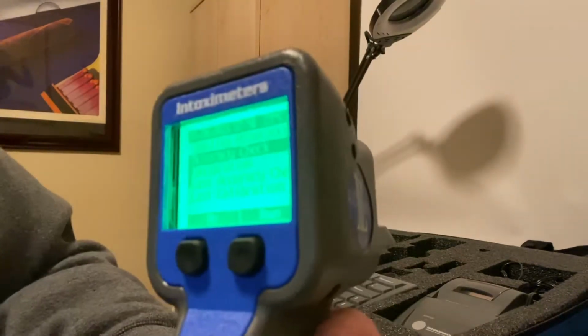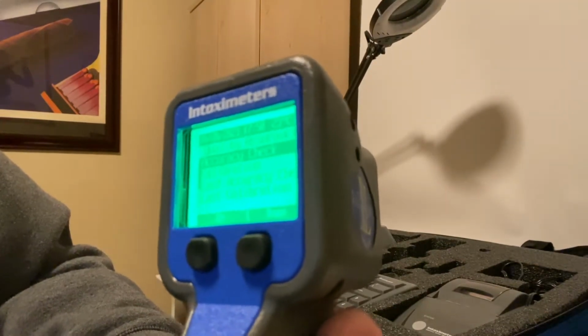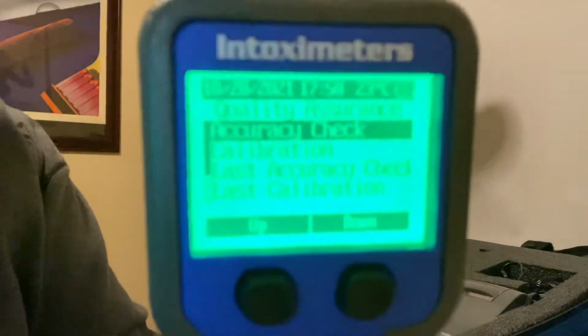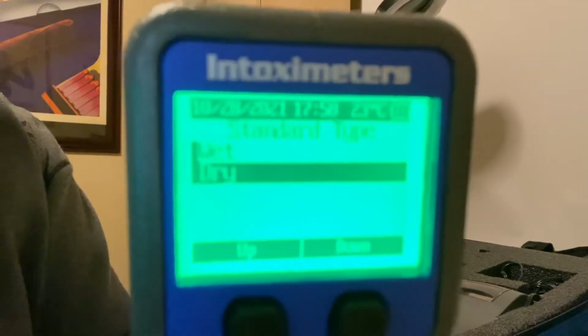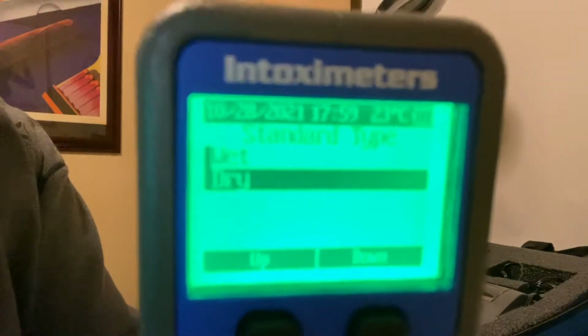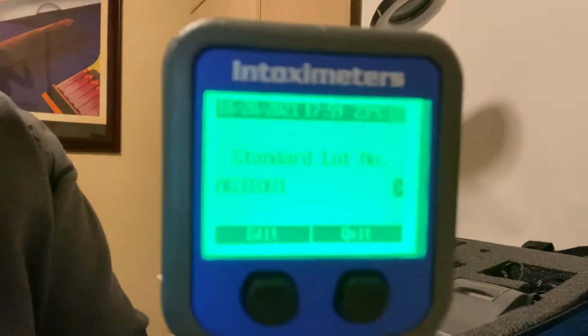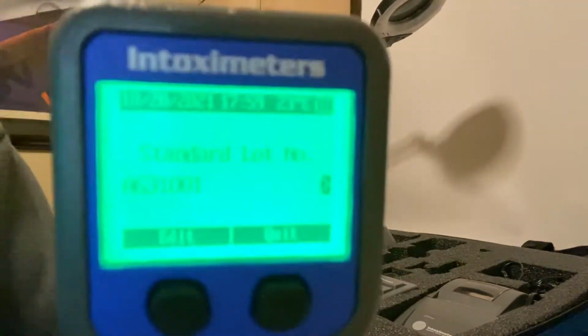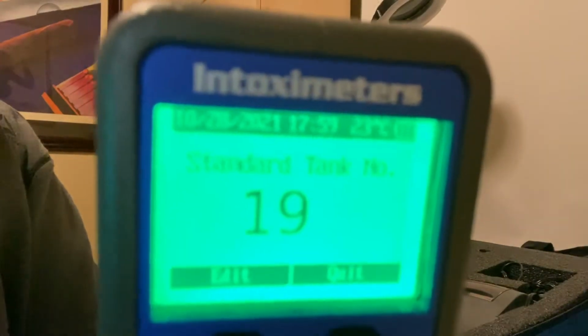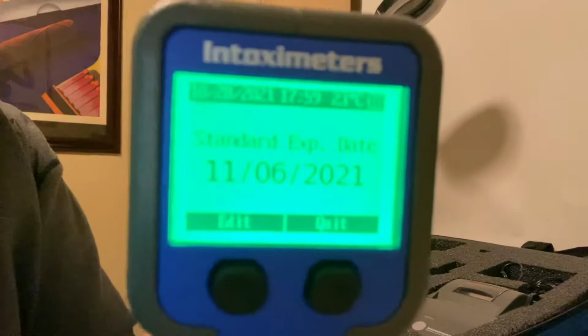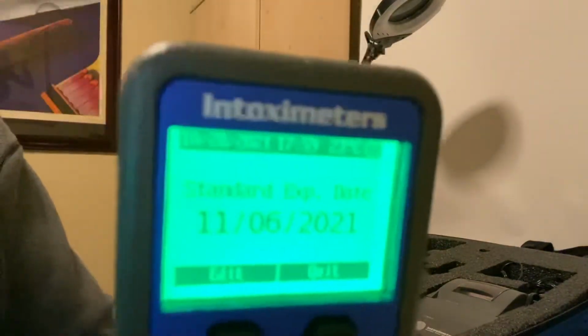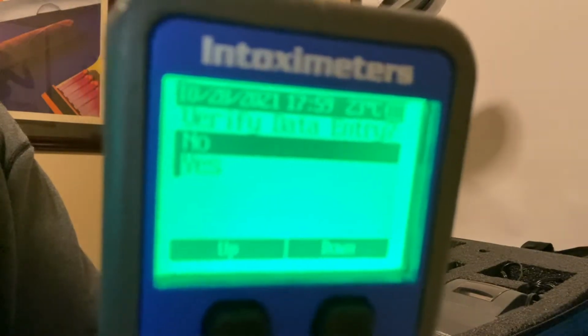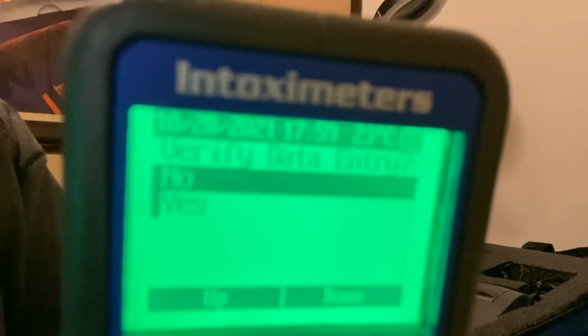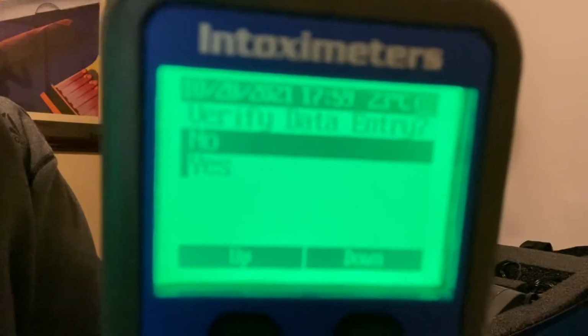Then it's going to come up accuracy check. You've got a couple other calibrations. So I'm going to squeeze the trigger and do accuracy check. It's going to ask me all the information that's on the tank, where it's a dry tank. So I'm just pushing the trigger. The lot number, so I'm pushing the trigger again. Tank number 19, and the expiration date, and then it wants me to verify the data. If I hit no, it will let me continue. If I hit yes, it's going to take me through the whole process of the expiration date, tank number, and all that. So I'm going to hit no.